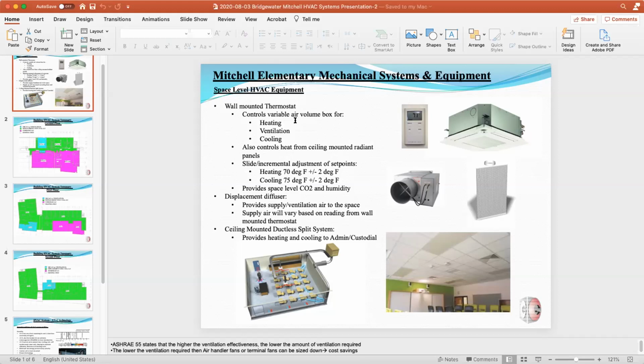We wanted to present what people would see within the space for controls. So essentially what we have here is, on the right-hand side, a thermostat, but it's actually going to be a multi-function sensor in a number of areas. It'll also show CO2 level and humidity. The thermostat controls a VAV box, which is right below that, essentially a box with a damper, and that's going to control the airflow in order to control your heating, ventilation, and cooling or air conditioning.